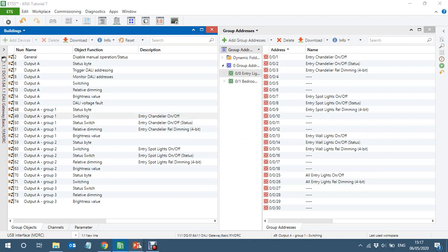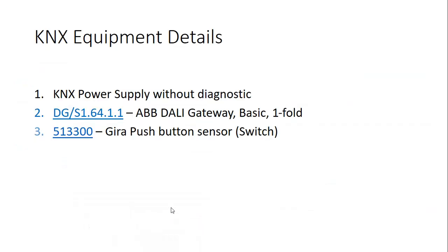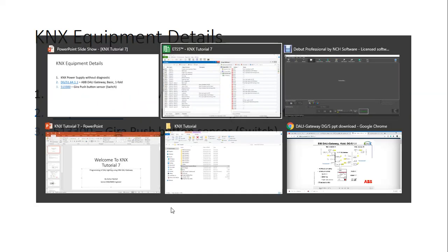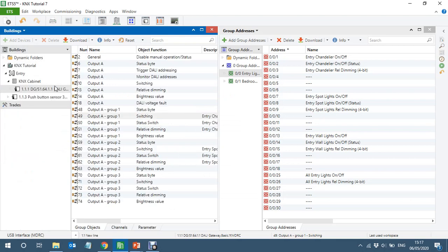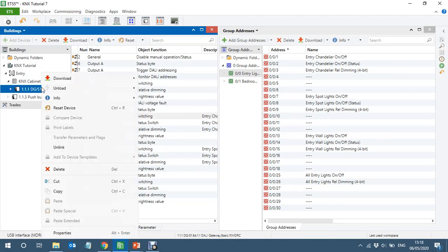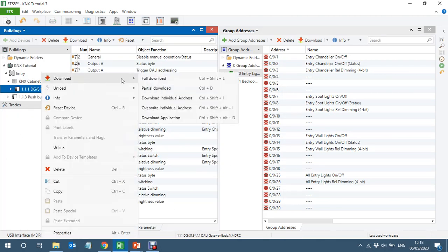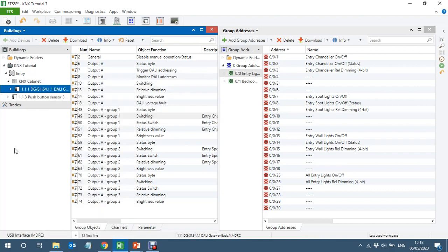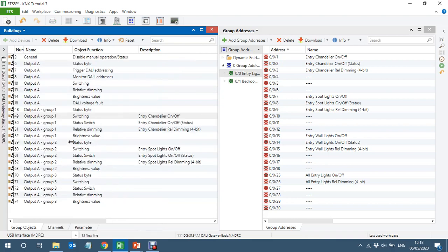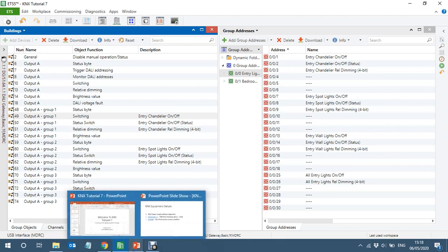And then you can control them. The rest of the programming exactly the same. Let's go back to the slides. The next thing is, once I've created these groups, I'll download this device, full download. I'll download everything to the KNX device. Now after downloading that device, nothing will work, nothing will work because you have to address the DALI light and group them to group one and group two which we are using in this example.